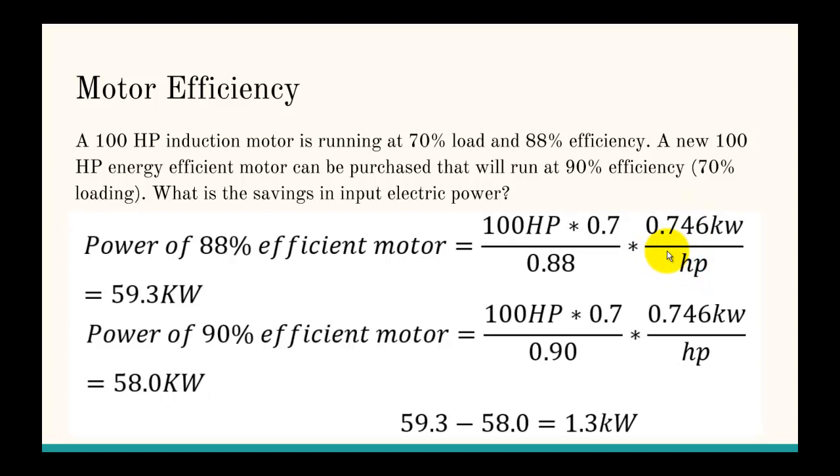So you get 59.3 kilowatts is what the original motor uses, and then you look at the 90% efficient motor. It's not that big of a jump in efficiency, so you actually drop your power usage to 58, and it's asking what is the savings in input electric power. So you have to subtract the two, which is 1.3 kilowatts.